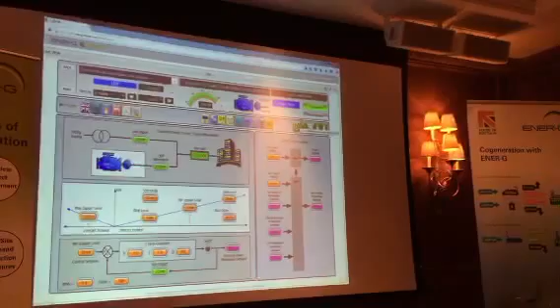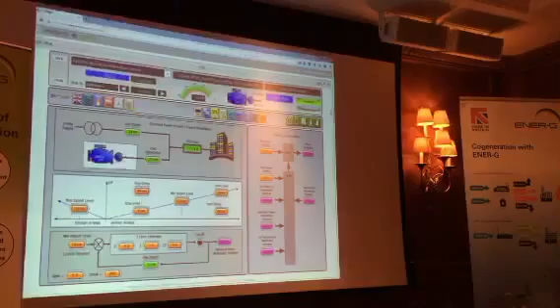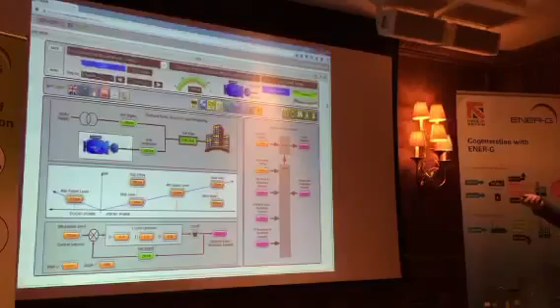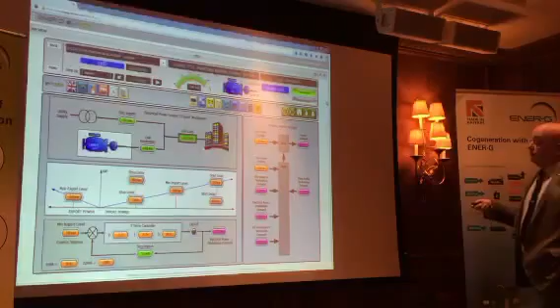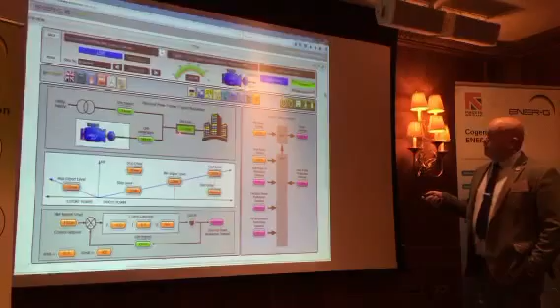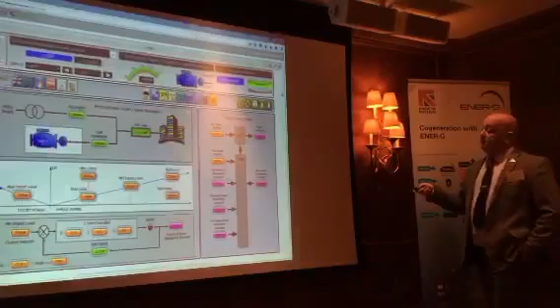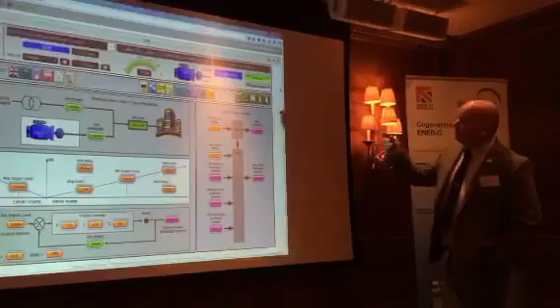One of the differences with ePower is that we tried to incorporate all aspects of the CHP package. With G control and with DERMS, it wasn't always possible to get a live view of heat rejection and building site loads. So what this graphic shows really is that we've taken a reading from the main building incomer, and the building as it stands at that moment requires 177 kilowatts of electric. So the generator we know is 150 kilowatt, and they're importing from the grid 28, 29. So it gives us a live view.